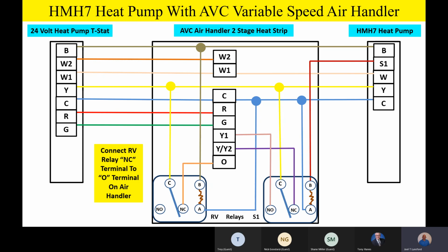Now, what happens when we go into the heating mode of operation, when we energize the B terminal from the thermostat for the reversing valve outside? We're going to switch that relay and we're going to break that O signal, telling the indoor unit, hey, we're in the heating mode on this heat pump. And that is correct. So we have to have that capability to energize and de-energize the O terminal during heating and cooling operations. So team, the only reason that RV relay is there is to ensure that the O terminal is energized in the cooling mode, and then the O terminal is de-energized in the heating mode. That's the only reason that RV relay is there, is to operate the signal for the O terminal.